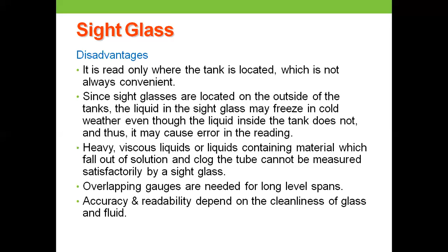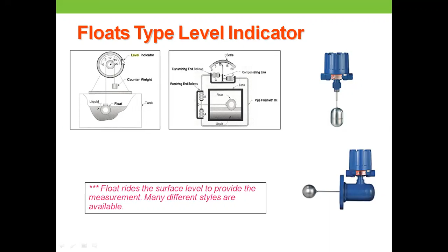Moving on to the float type of level sensors. Here, the level indicator is utilized over the tank, and this is a pictorial representation of it. When the liquid has been filled over it, this particular float will be raised in the upward direction due to the buoyancy forces, and it is balanced with respect to the counterweight or balancing weight. Due to the buoyancy forces, this float will be raised upward, and depending upon that, the indicator will show the level on the analog display screen, right? This is the working we have just discussed.